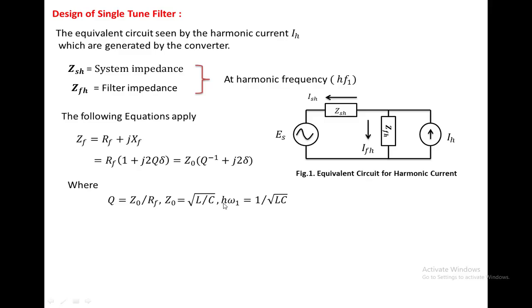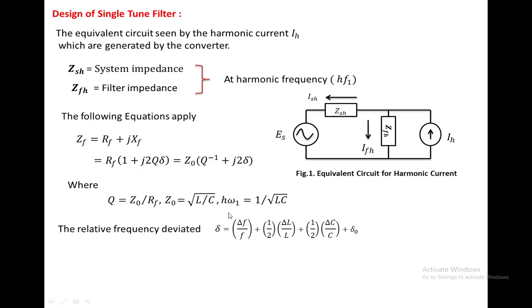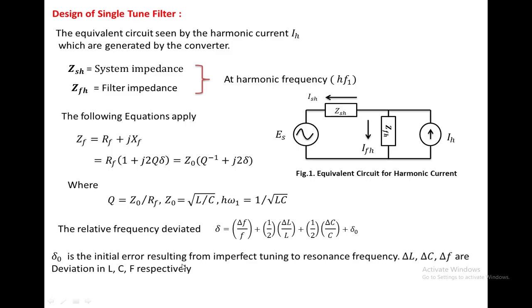H is the harmonic order. The resonance condition is: H·omega1 equals 1 over root(LC). The relative frequency deviation delta equals delta_F over F, plus one-half·(delta_L over L), plus one-half·(delta_C over C), plus delta_0. Here delta_0 is the initial error during tuning of the resonance frequency, and delta_L, delta_C, and delta_F are the deviations in inductance, capacitance, and frequency respectively.